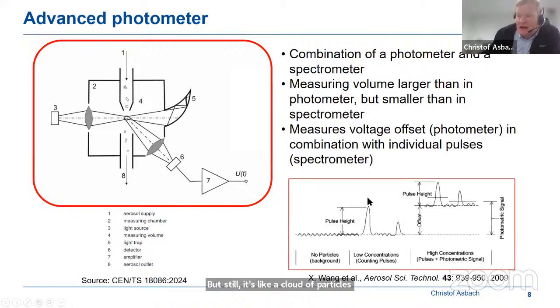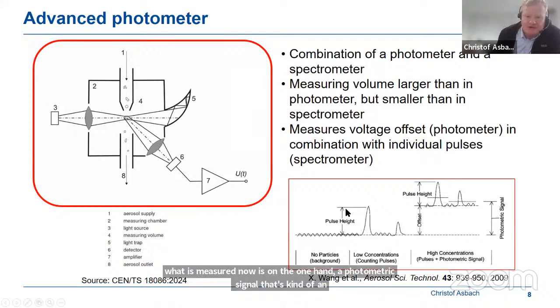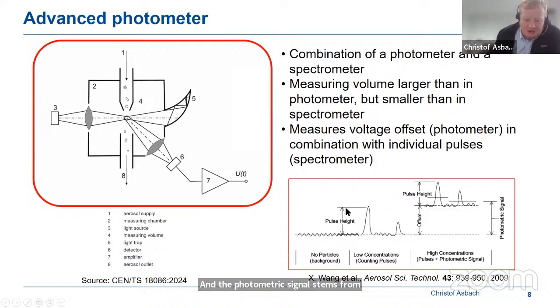And what is measured now is, on the one hand, a photometric signal that's kind of an offset. And the photometric signal stems from the very large number of small particles which are present. And if you look at typical size distributions, then you typically have a lot of small particles and a few large particles. And the few large particles of different sizes actually are mostly responsible for the mass concentrations, whereas the large number of small particles only gives kind of the baseline of the mass concentration. And that's what this exploits.